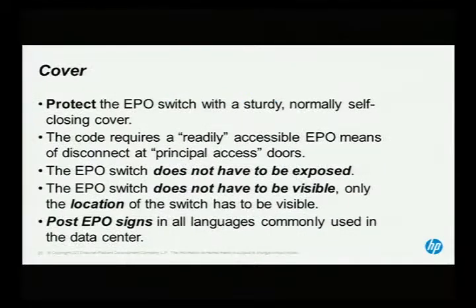Cover it. All right? There's nothing in the code that says the disconnecting means, the EPO switch, has to be easy to use. Okay? It doesn't have to be exposed. It doesn't have to be visible. Only the location of where it's at has to be visible. You could put a big sign up here that says disconnecting means, with an arrow to a cover panel.